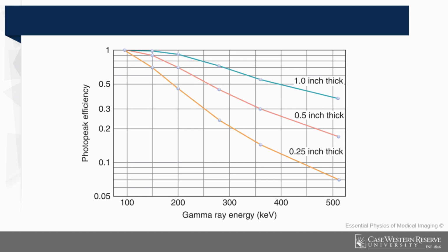The other thing is the thickness. So you need a thick crystal to stop high energy gamma photons, to give you good efficiency. But if they get thick, remember those scintillations, they bounce back and forth. At a point, it can become a halo, so you lose some of the resolution. So for high resolution, you need a thin crystal. Of course, the problem of the thin crystal is the efficiency. Higher energy gamma photons will shoot through without scintillation, so you will lose some of the efficiency.